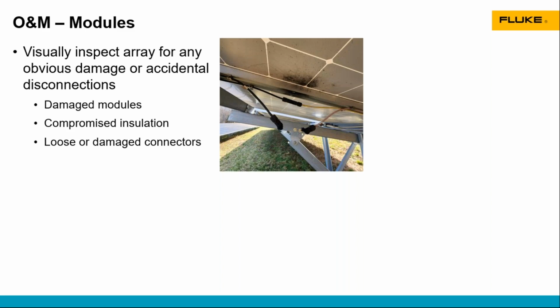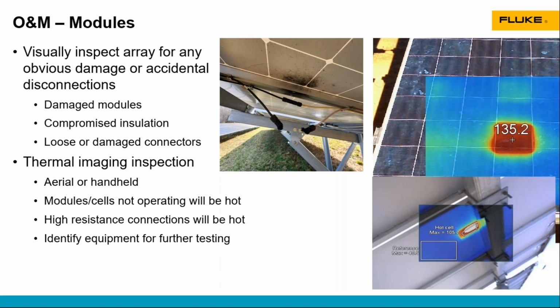Maybe the connection when it was made in the field was done poorly, or it could be that some contamination like dirt or debris or insects got into the connectors before they were connected together, or it could be that the person just didn't plug them in all the way and there was a high resistance connection there that burnt out. We can also use thermal imaging to find issues with our array.